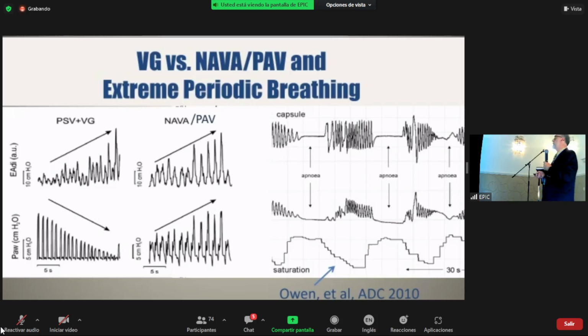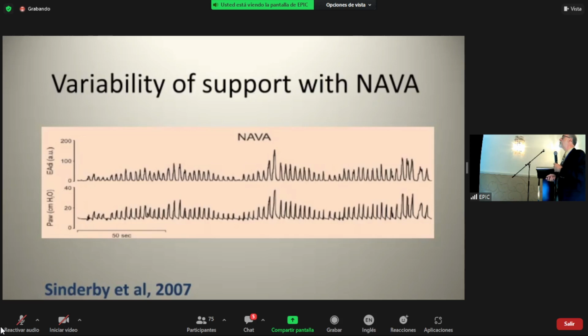So I know some of you here on the island have the servo machines. I don't know if you all have the NAVA module, but this is the problem with NAVA. The promoters of NAVA are very proud of the fact that the pressure generated by the machine very closely tracks the effort of the baby. So baby hypoventilates, not much support. Baby breathes more normally. Okay, we're good here for a while. Hypoventilates again, not getting any help. Then there's a vigorous inspiratory effort generating a pressure close to 40 centimeters. So up and down. So it's accentuating the immature respiratory control, the highly variable respiratory effort on the part of the baby. And I think that's a dangerous thing.